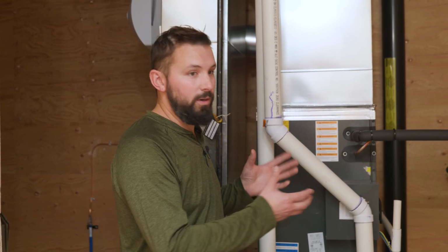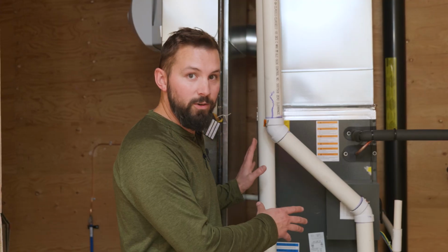Some settings on these furnaces are going to cause them to consume 125 watts. Some settings, based on the duct design, are going to cause them to consume 75 watts. That's a pretty broad range, and we could be reducing our energy draw by 50 watts 24 hours a day if we make the correct decisions when we design our ducts and when we install our ducted system.